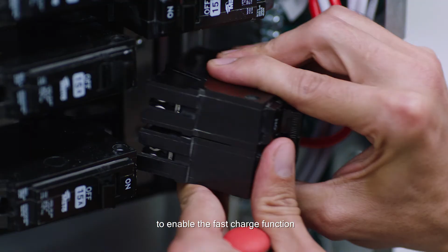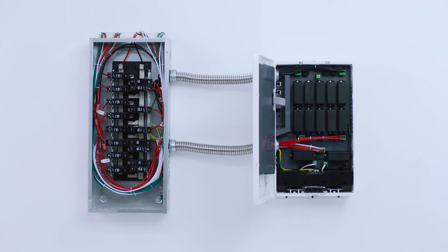To connect the outputs, connect each load hot wire to the corresponding wires from the smart home panel using wire nuts. Repeat this connecting process for all 10 circuits. The smart home panel has the option for a split phase setup with 240 volts, which requires 2 Delta Pro units. Each Delta Pro takes up to 5 of the circuits once the switching connector is removed. The same phase connection should be mirrored in the smart panel and the load center.